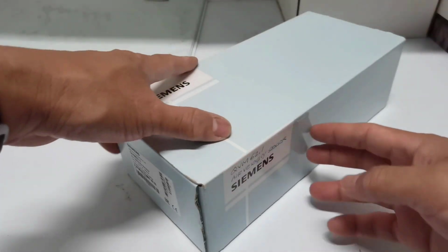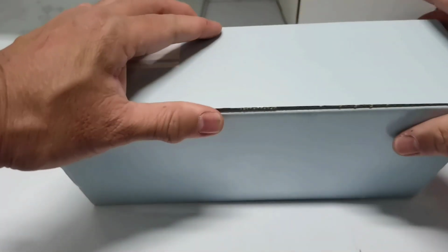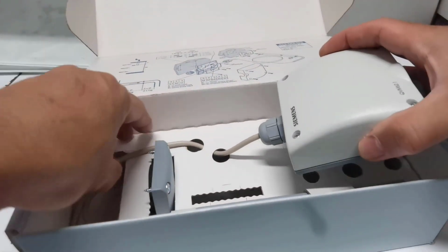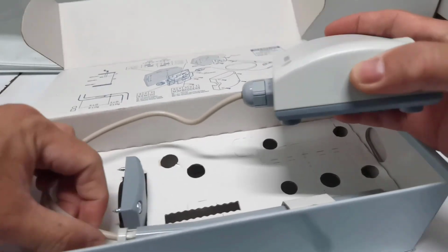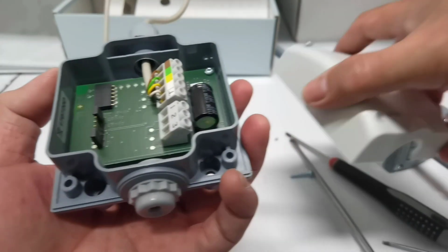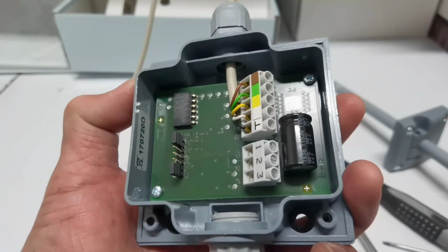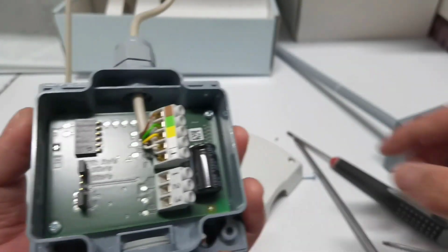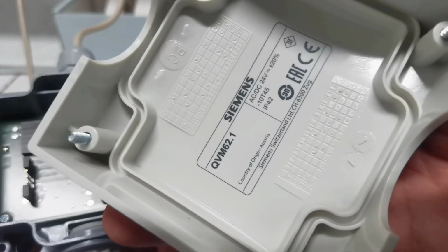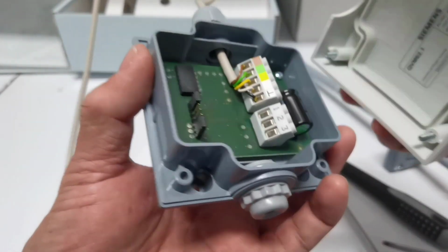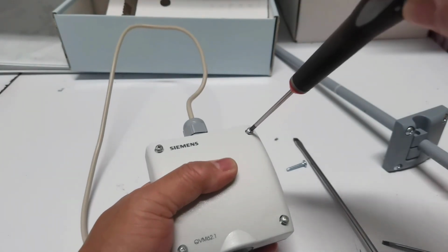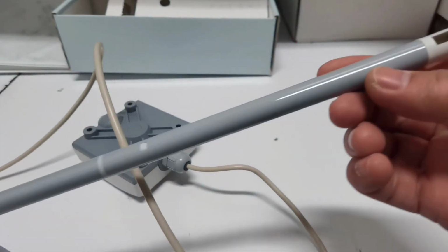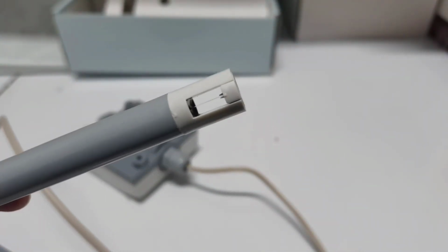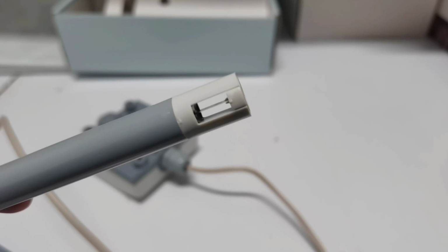This is the QBM 62.1 air velocity sensor, used to control the air velocity to a constant value, or to balance out pressure fluctuations, or to monitor the flow in the air ducts. The QBM 62.1 records the air velocity as a measured value and converts it to an active DC 0 to 10 volts or 4 to 20 milliamp output signal. 3 measuring ranges are available: 0 to 5, 0 to 10, and 0 to 15 meters per second. The specially developed thin film sensing element of the QBM 62.1 is to a large extent independent of the flow direction and is nearly insensitive to any kind of dirt in the airflow.